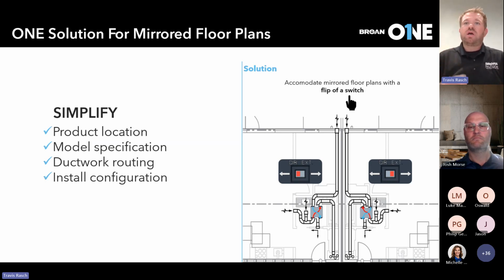And finally, from an install standpoint, if we got a high-rise building, we got 200 going in, it can be very repetitive work. You have the ability from a contractor standpoint, whether you got a newer person on the job, it's always going to be consistent as to how this thing is going to physically mount, where it's going to physically mount, how the ductwork is going to get pretty simple as it relates to that. So the layout, again, we're eliminating that quote unquote creative freedom out in the field. It's pretty well defined, all because of this in-field selectable airflow configuration.